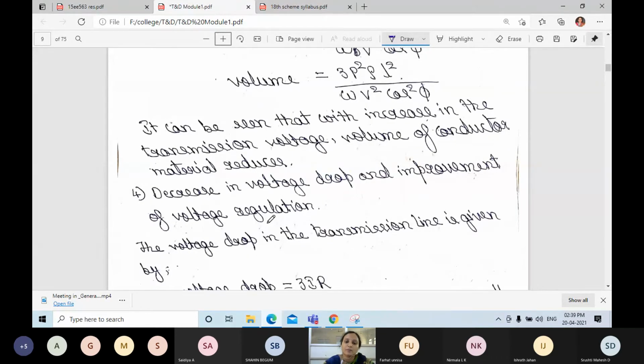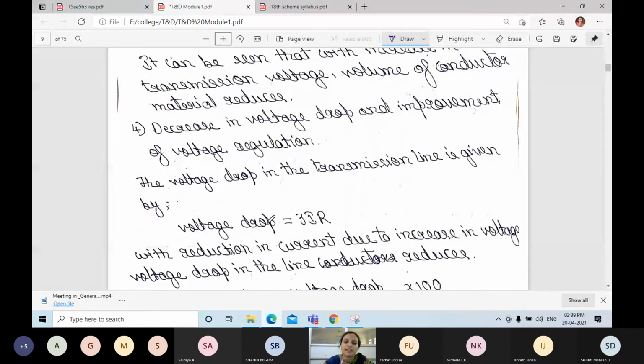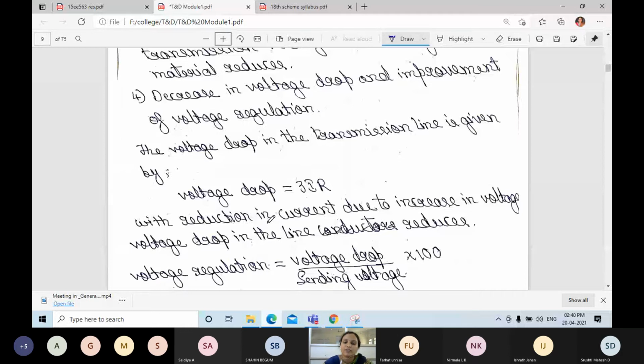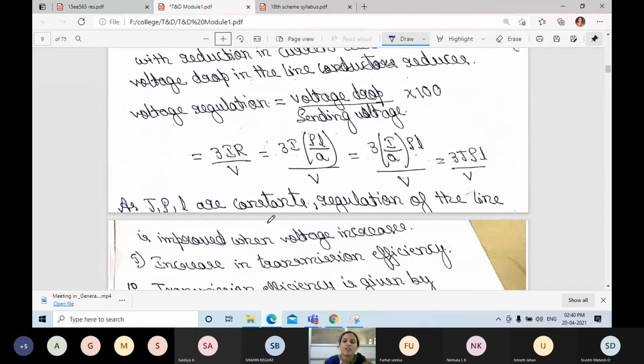Next, the voltage drop and improvement of voltage regulation. The voltage drop in the transmission line is given by voltage drop is equal to 3 into I into R. If the current is reduced due to the increase in voltage, the losses will be reduced. Voltage regulation is the voltage drop divided by the sending voltage into 100, which gives the formula 3 I rho L divided by V. Here everything else is constant and V is inversely proportional. If we increase the voltage level, the voltage regulation will be improved. The regulation of the line is improved when the voltage increases.